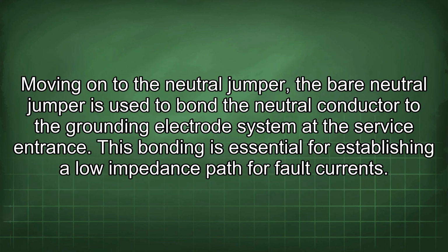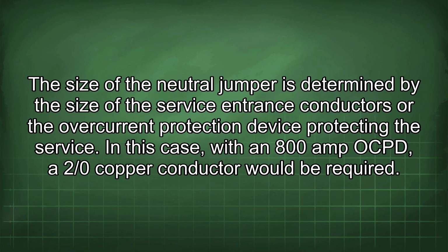Moving on to the neutral jumper. The bare neutral jumper is used to bond the neutral conductor to the grounding electrode system at the service entrance. This bonding is essential for establishing a low impedance path for fault currents. The size of the neutral jumper is determined by the size of the service entrance conductors or the overcurrent protection device protecting the service. In this case, with an 800 amp OCPD, a 2/0 copper conductor would be required.